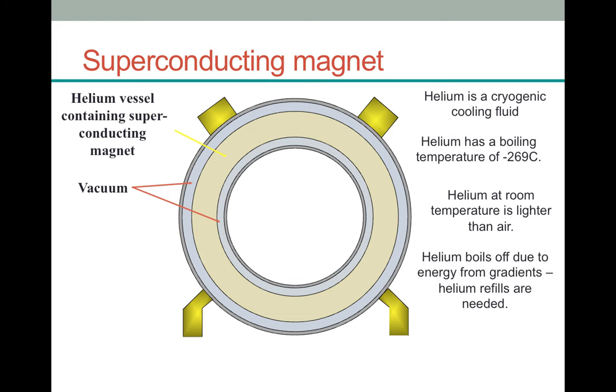The magnetic coil sits in liquid helium, which is used as a cryogenic cooling fluid. Helium at room temperature is lighter than air, which is why balloons filled with helium float to the ceiling. Helium has a boiling temperature of minus 269 degrees centigrade, which is needed to keep the magnet very cold. The gradients send energy into the machine to get the signal we're interested in, and the magnets heat up and a small amount of helium boils off. These magnets are very expensive because of the amount of helium they use — even when the MRI unit is doing nothing, it is still using up helium, although in very small amounts.